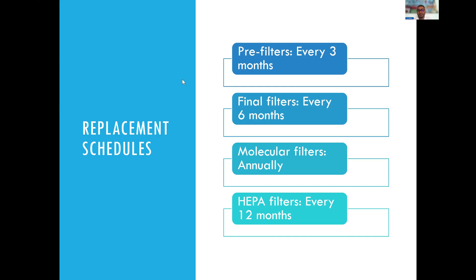Total cost of ownership is very important when we're talking about a facility that spends a lot of resources on energy conservation. It's always good to have an idea of the total cost of ownership. And what is total cost of ownership? It just takes into account the full cost of owning the filter. This takes into account the actual cost of the product, the disposal, how much time it takes to change the product, and the energy cost associated with running that product to the full extent, which could be 1.5 on the magnehelic, or in some cases 1.0 on the magnehelic, versus changing it maybe when it's at 0.8 or 0.9.